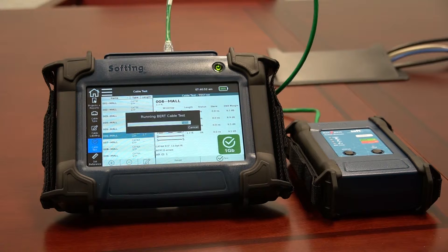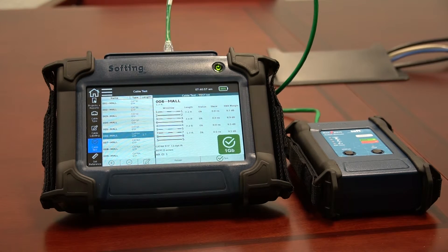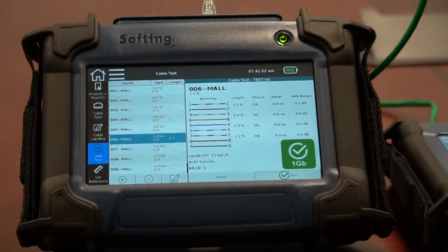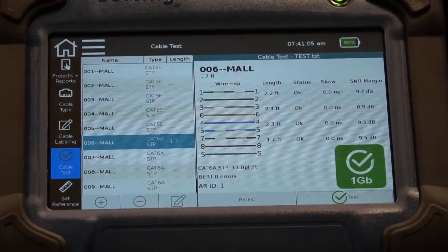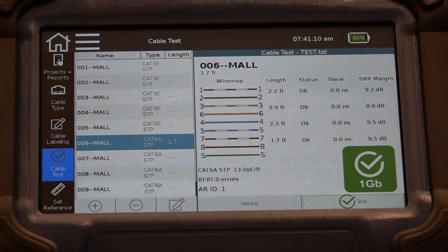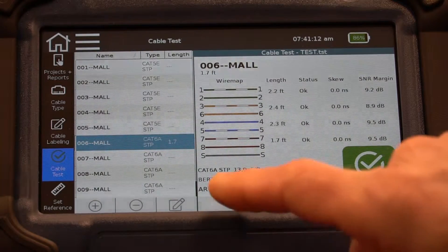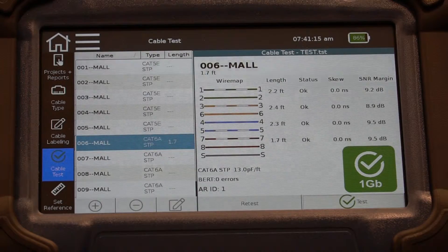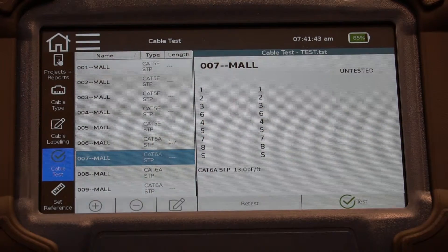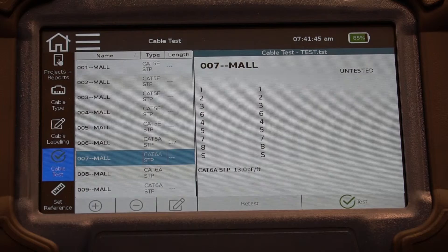It passed the test. It runs all the tests and then gives you a summary of whether it passes or fails. You can see the results here: the wire map, the length of the cable, the status, the parameters for skew and signal-to-noise ratio, and it also tells us we had 0 bit error rate test errors. When you're ready to test the next cable, just select the next test in the list and hit Test — it's pretty simple to go down through your cable list and complete your project.